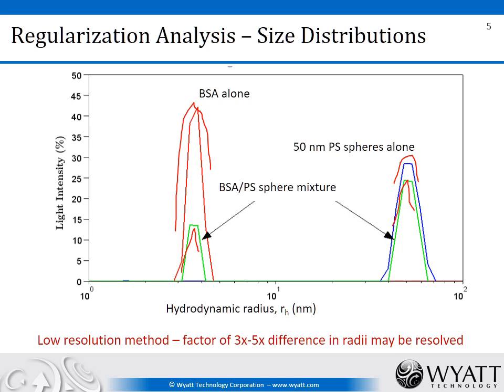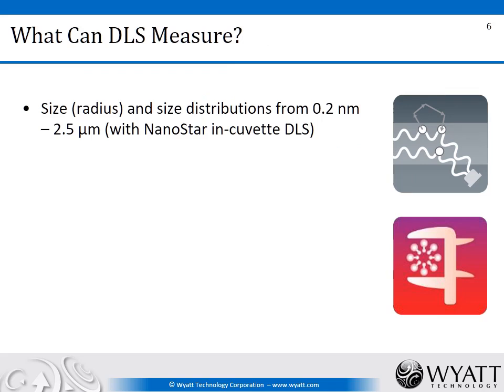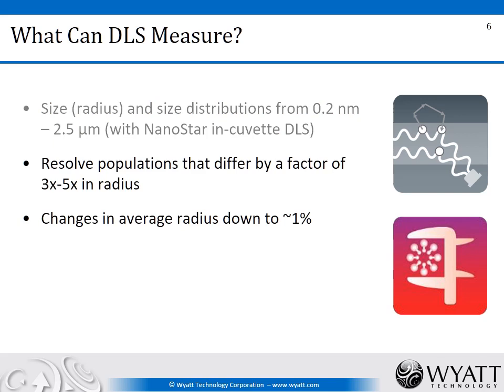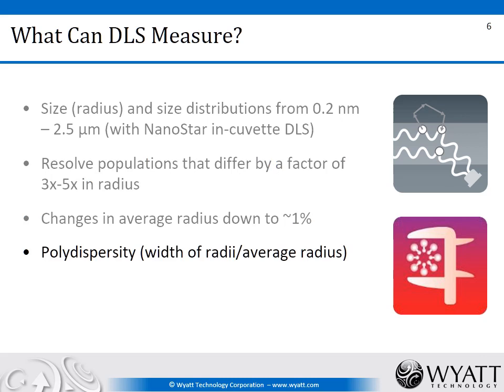DLS is a low resolution method. In order for peaks to be resolved, populations need to differ in size by a factor of at least three to five. Dynamic light scattering can measure size and size distributions covering radii from 0.2 nanometers all the way up to 2.5 microns using standard cuvette-based DLS, such as the DynaPro NanoStar. You can resolve populations that differ by a factor of three to five in radius. Even with a single population, you can measure changes in average radius down to about 1%, and also measure polydispersity.